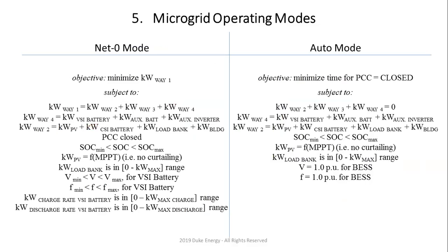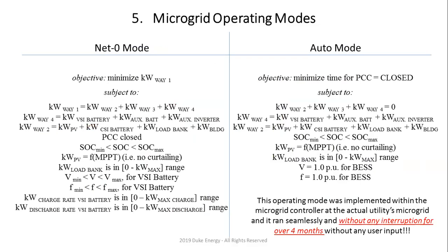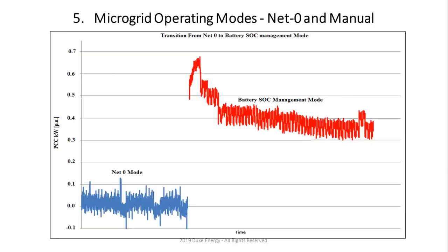Okay. So now, probably one of the most challenging parts: how does the microgrid operate, right? Well, we have several modes, right? We have manual mode, we have net zero mode, which means that we try to keep kW at 0 at the PCC, and we have auto mode on the right side. So most of the time we operate in auto mode, right? And using this mode, we actually stay anywhere between 21, 22, 23 hours off the grid, right? We ran it in this particular mode over 4 months without any user input, and then we actually had to stop it because we were adding a generator and microturbine, right? So this particular system works, right?